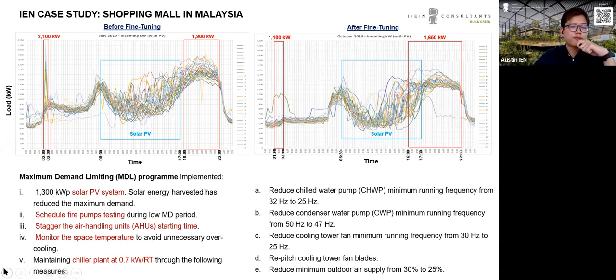First, we have about 1.3 megawatt solar PV in this mall. We schedule the fire pump testing during the low maximum demand period, stagger the AHU starting time, monitor the space temperature to avoid unnecessary overcooling, and maintain the chiller plant at 0.7 kilowatt per ton through the following measures.